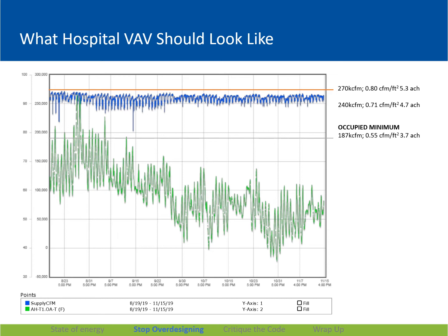The average code minimum that you're going to find throughout hospital buildings is about 0.5 to 0.55 CFM per square foot, or 4 air changes per hour, 3.7 air changes per hour for the volume of the space that you're looking at. In California, we can drop this off a little bit because we have some different rules in the patient rooms, but that's not a huge effect. Generally, that's a number that you should be targeting for your occupied code minimum.